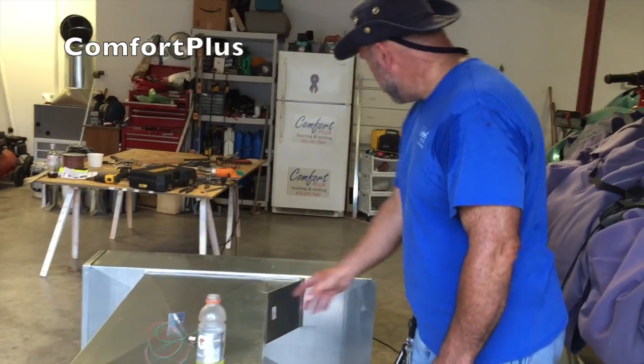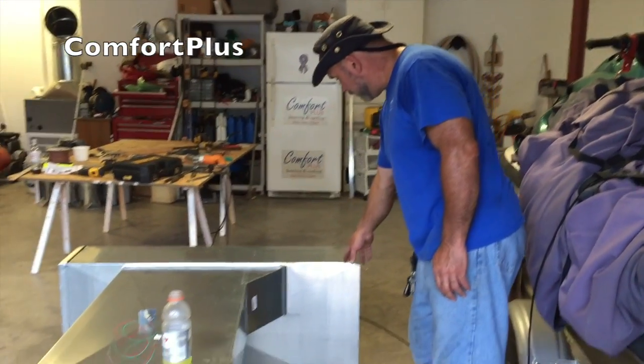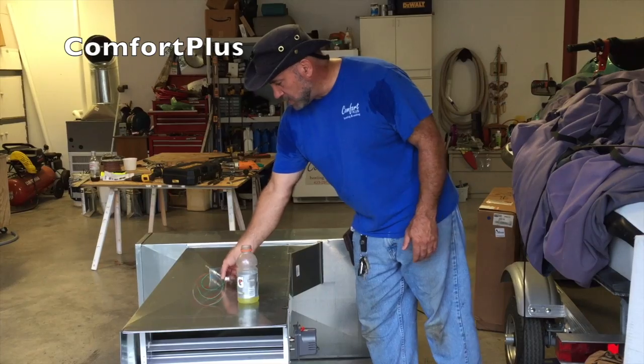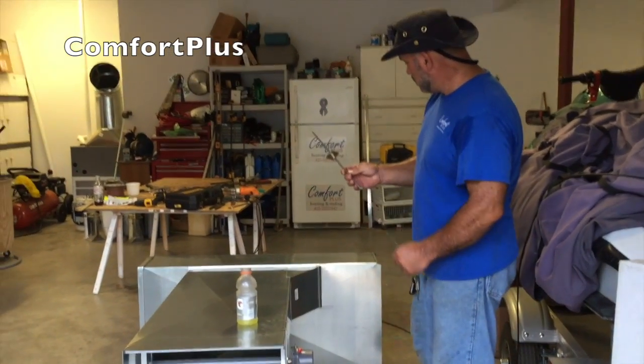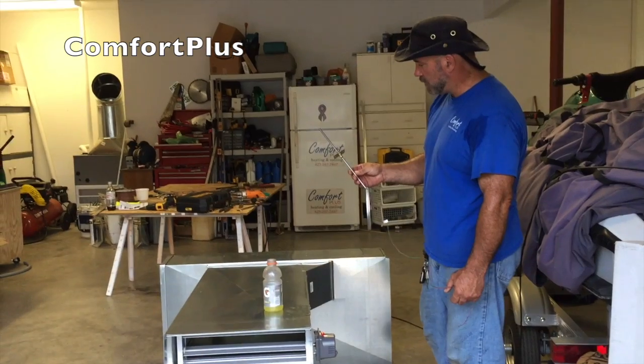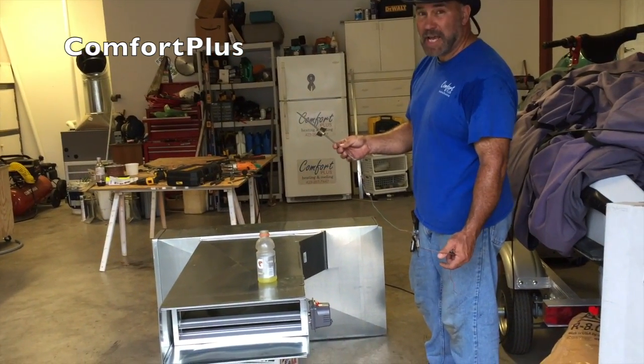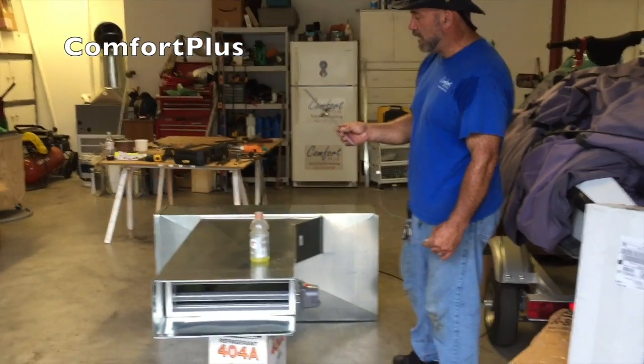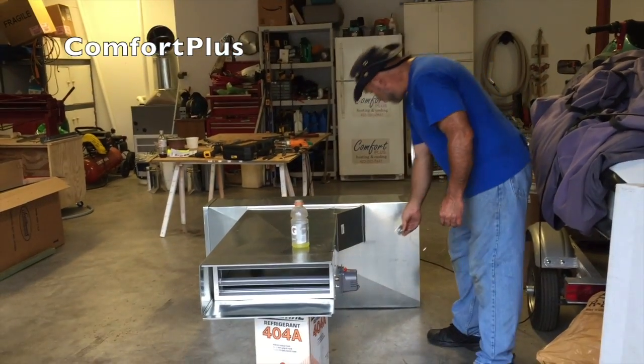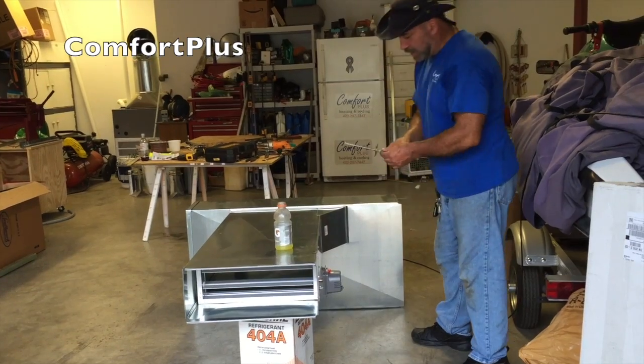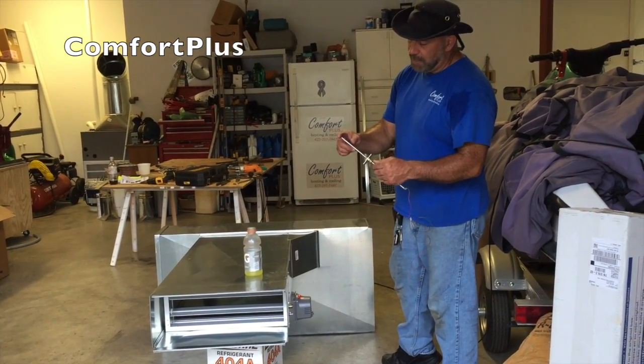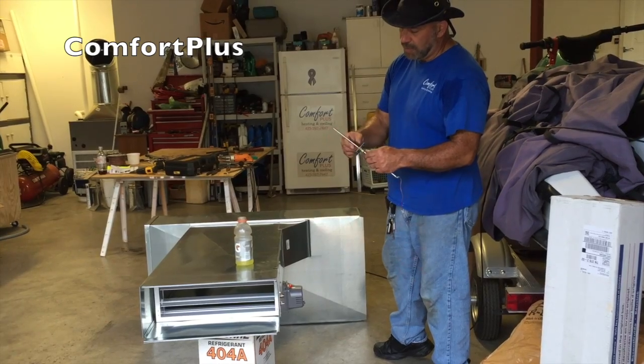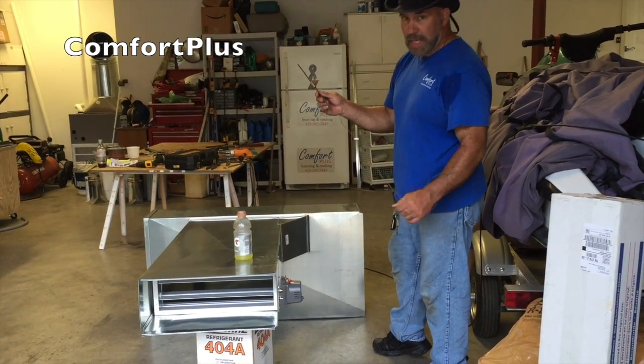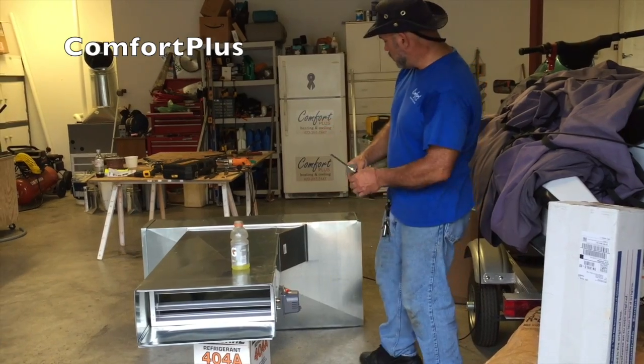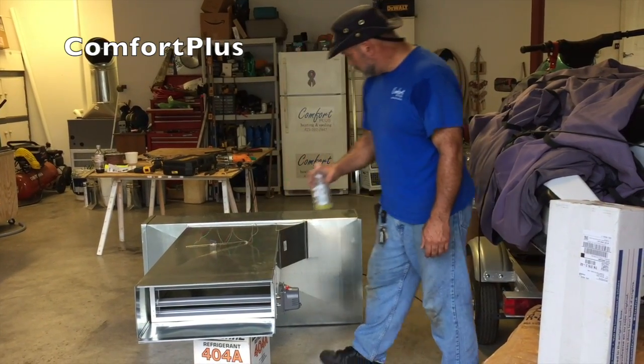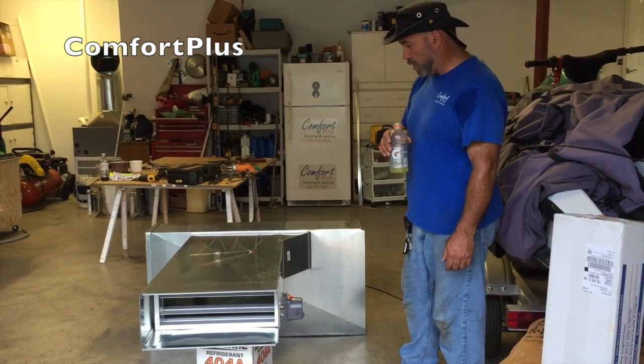I made a transition to go from my air handler to this trunk duct. The length of the transition, I basically decided to make it the length I did based on this temperature sensor. The only limitation they had in the manual was this temperature sensor should be 19 inches away from the air handler. So that will put it right in this general area. It's adjustable so that you can put the tip of it halfway into the duct. I'll have to adjust this one very slightly. I won't put it in until I'm underneath because I don't want to take a chance on damaging it. But all in all, the hard part is about over.